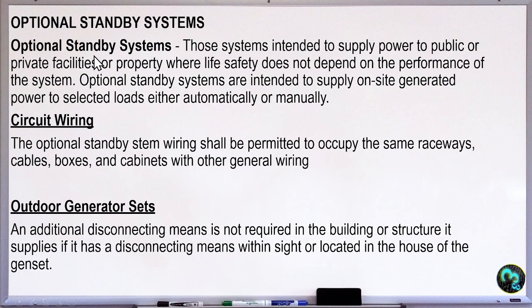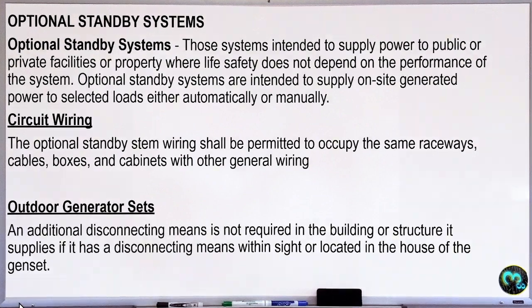Optional standby system. So optional standby systems are those systems intended to supply power to public or private facilities or property where life safety does not depend on the performance of the system. Optional standby systems are intended to supply on-site generated power to selected loads either automatically or manually. They call it a portable generator, which is only used, for example, when a school has a program, or there is an outreach program by the government in areas without electricity. So these are optional standby systems. The circuit wiring is the same as the normal wiring system. Then the outdoor generator set and additional disconnecting means is not required in the building or structure if the generator has a disconnecting means within sight or located in the house of the genset.